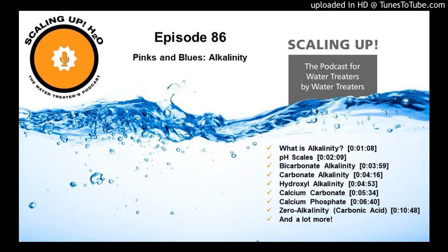So like everything, things evolve, things get better, and now we use bromocresol green, which will be green at 8.3 or anything above 4.3 actually. And we titrate that down to 4.3, and at 4.3, that green solution turns to red. And folks, it's really easy to see green and red, so that's why we use bromocresol green. But we don't call it B alkalinity. We still call bicarbonate alkalinity M alkalinity, I guess because we're honoring the methyl orange.